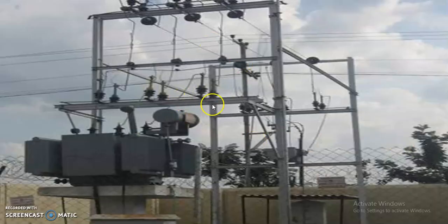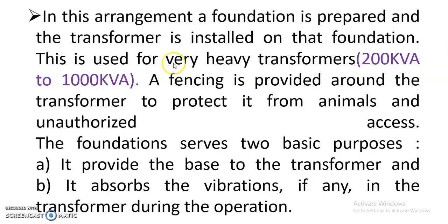So this is our simple layout of the plinth mounted substation. This transformer is placed on the plinth which is made up of cement concrete. In case of a pole mounted substation, the transformer is mounted on the pole, that is the H pole structure. But in this case your transformer is heavy, so you have to mount that transformer on the cement concrete structure. So in this arrangement, the foundation is prepared and the transformer is installed on the foundation.